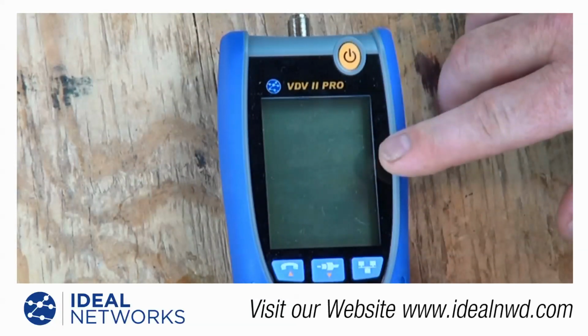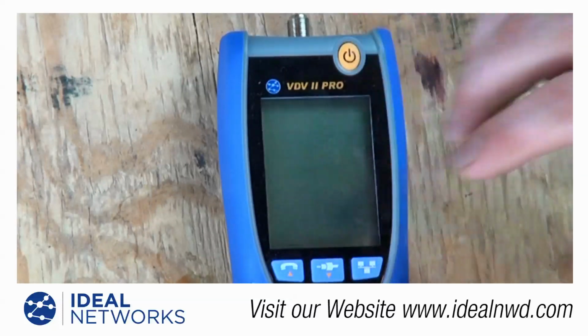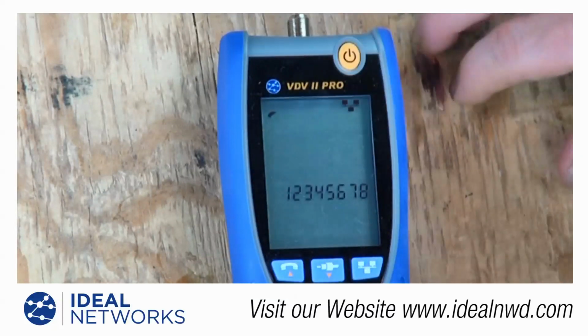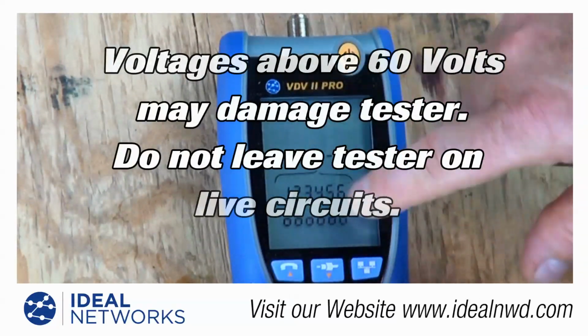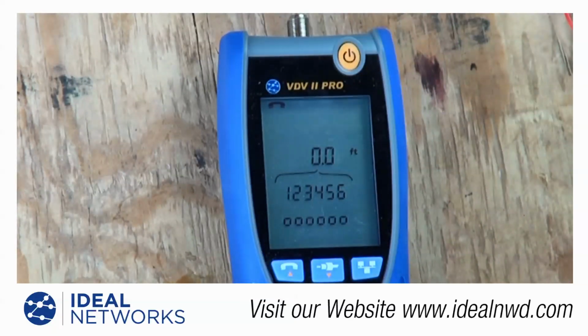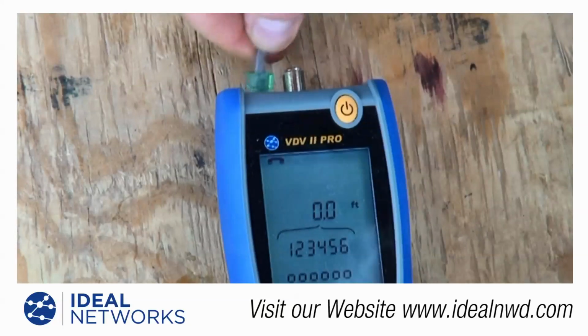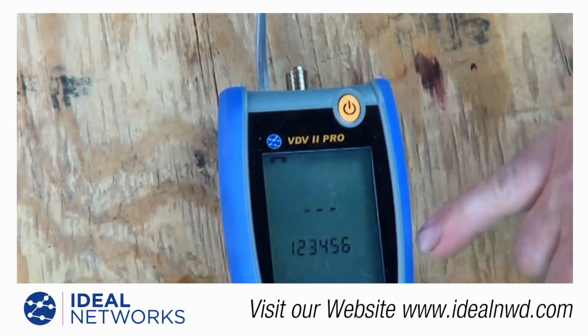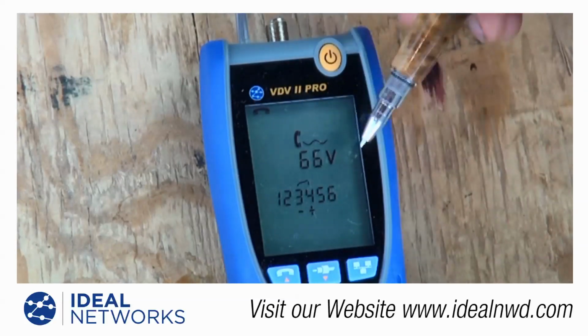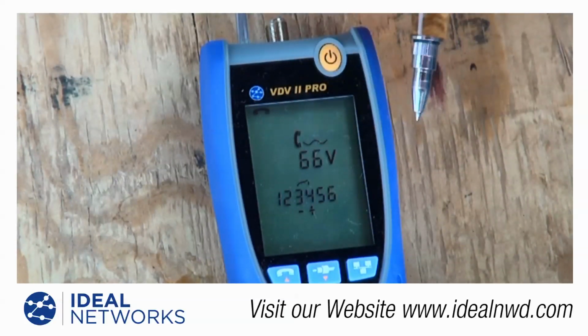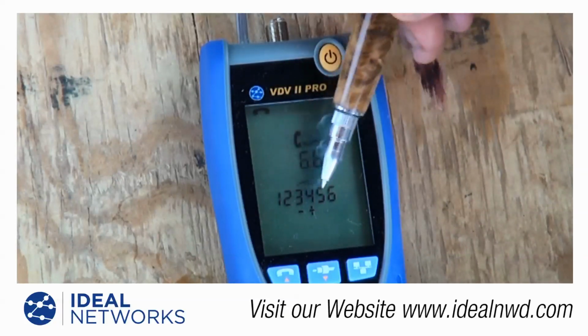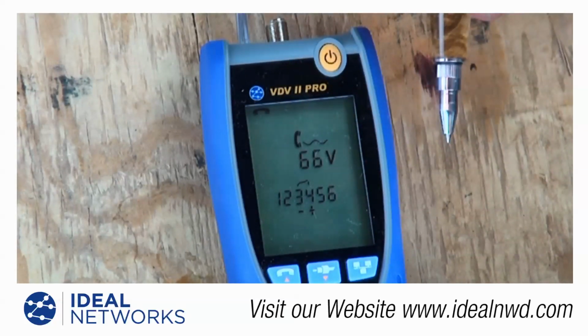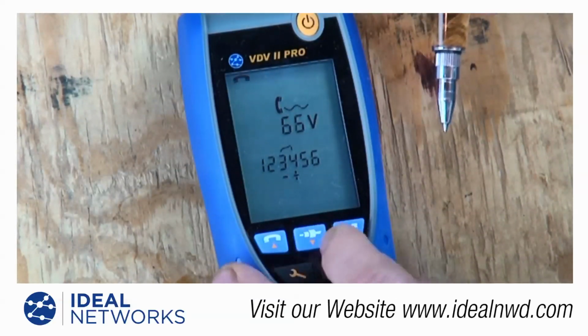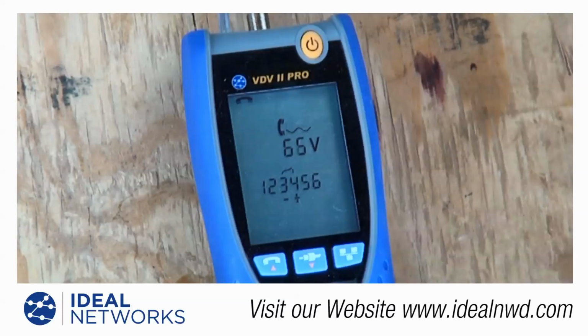The VDV Pro is over-voltage protected and can indicate certain voltages if it recognizes them. When you turn it on, it automatically goes into a mode — I'll switch it to phone mode. Now it's looking for a phone line and shows nothing since there's no voltage present. But if I plug an active phone line into the tester, it indicates it sees voltage, about 66 volts of analog phone service, on pins 3 and 4, showing the positive and negative of that DC voltage. The tester is now frozen — no other function will work because it sees that voltage, and it won't let you do anything else with the tester.